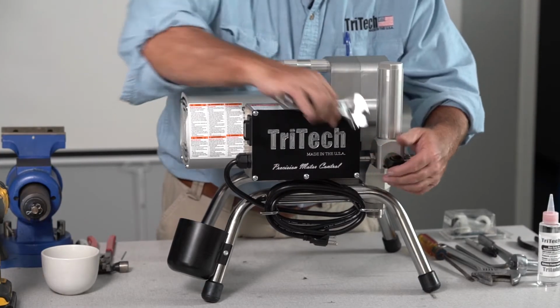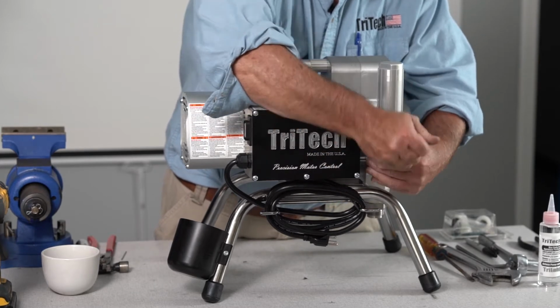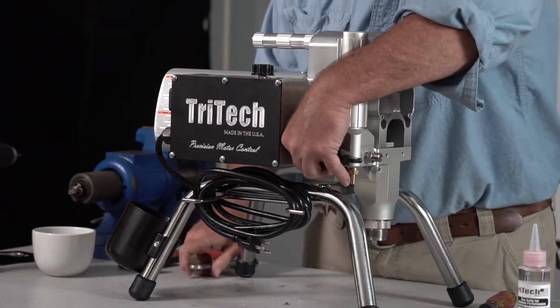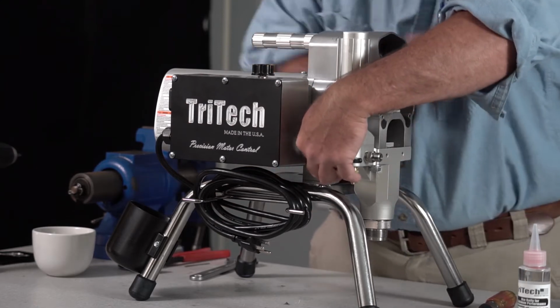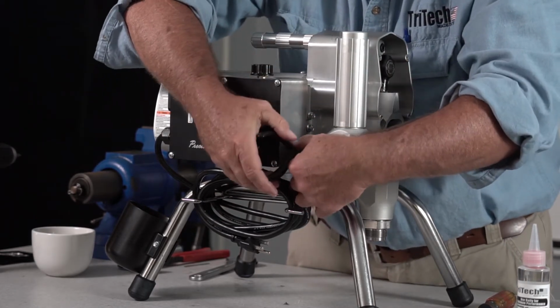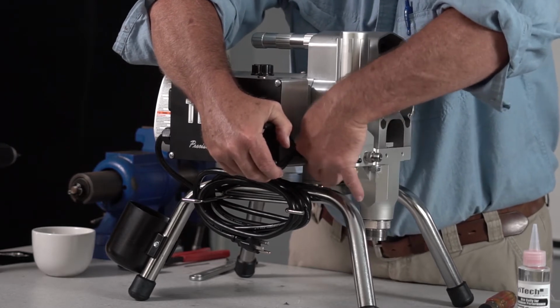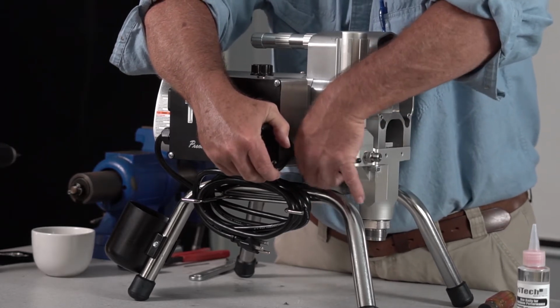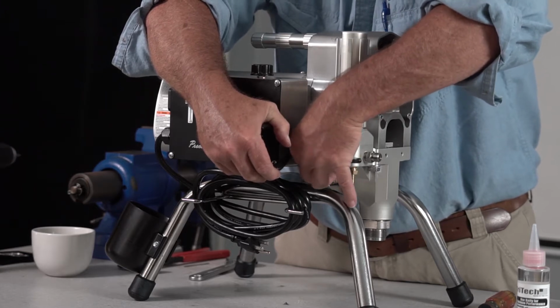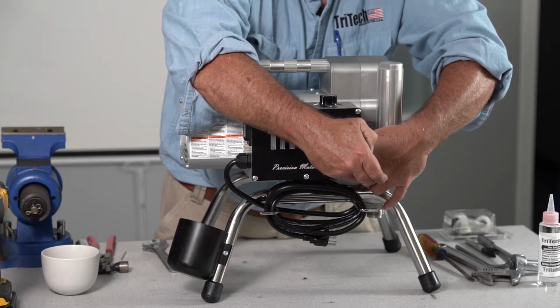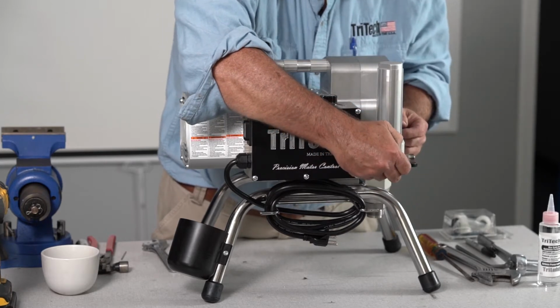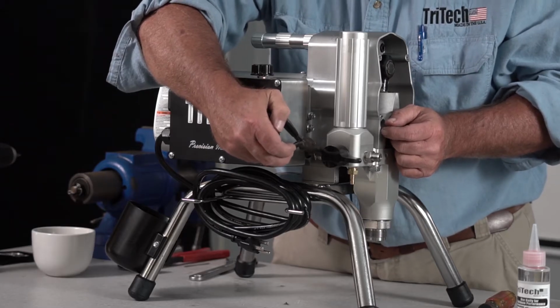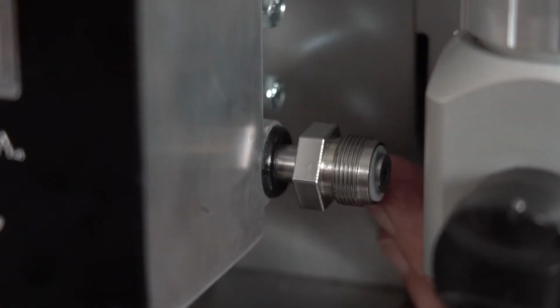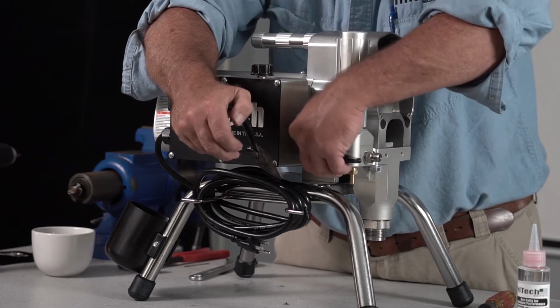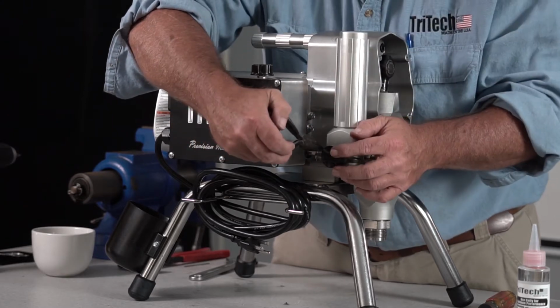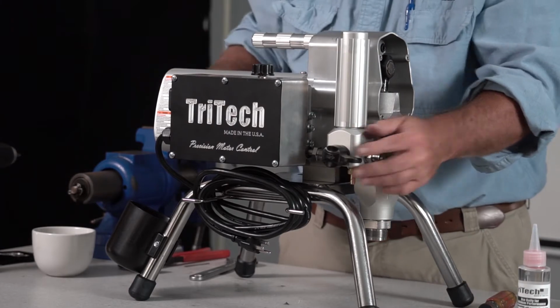First thing we want to do is loosen and remove the transducer from the fluid manifold. So we loosen our retaining bolt. And then you want to grab a pair of needle nose pliers and just hold on to the shaft to make sure that the transducer shaft doesn't turn as you're unthreading it. Once that's done, you pull it out. You want to make sure that your transducer gasket is in place, that you can visually see it, and that it's on the transducer. Sometimes they may get stuck inside the fluid manifold, so ours is right here. That's a good spot for it to be.